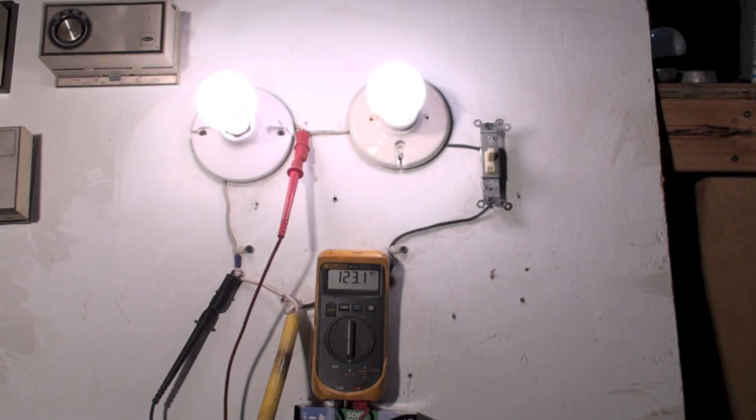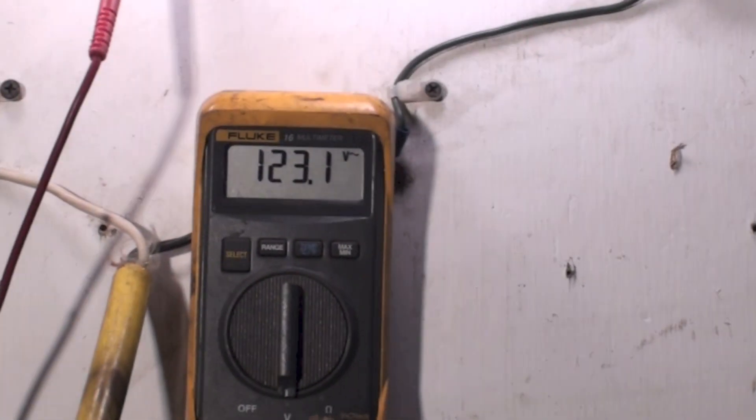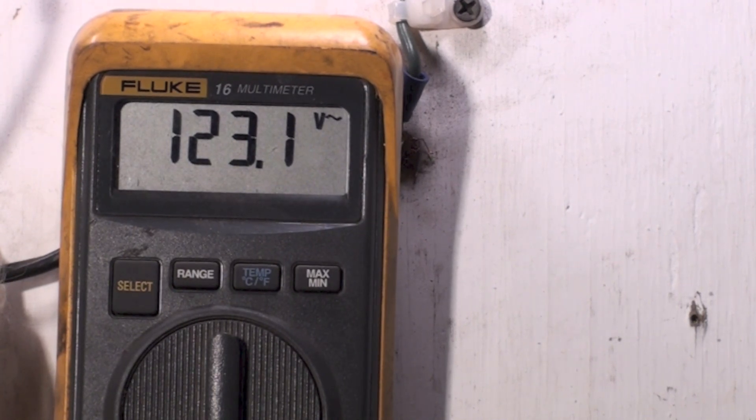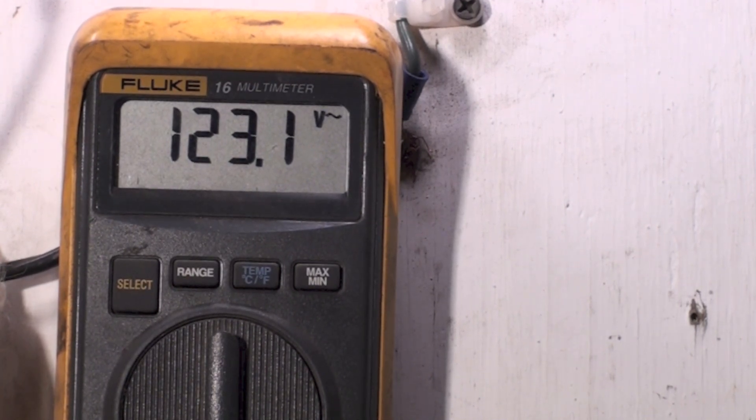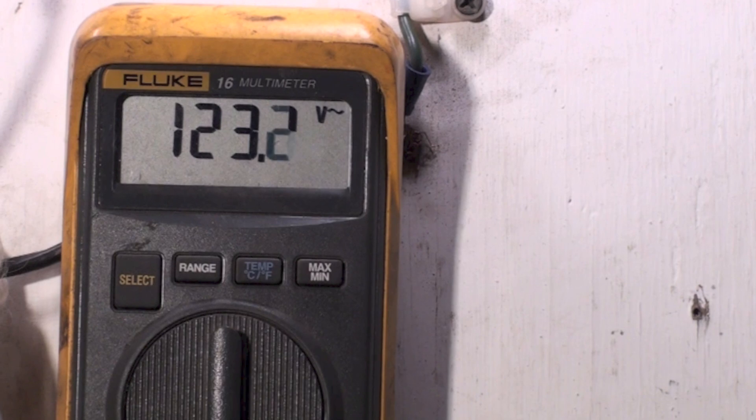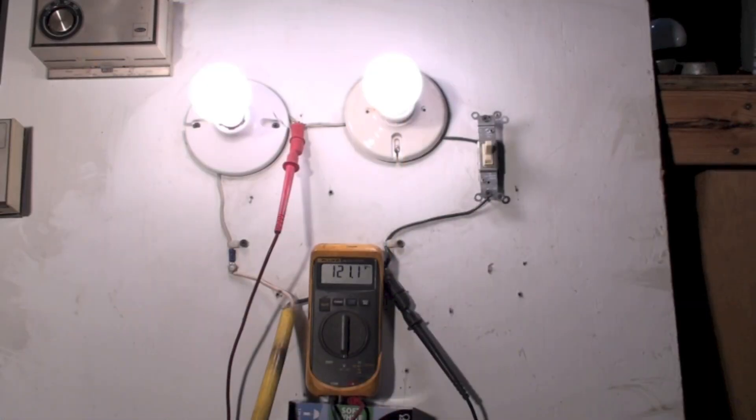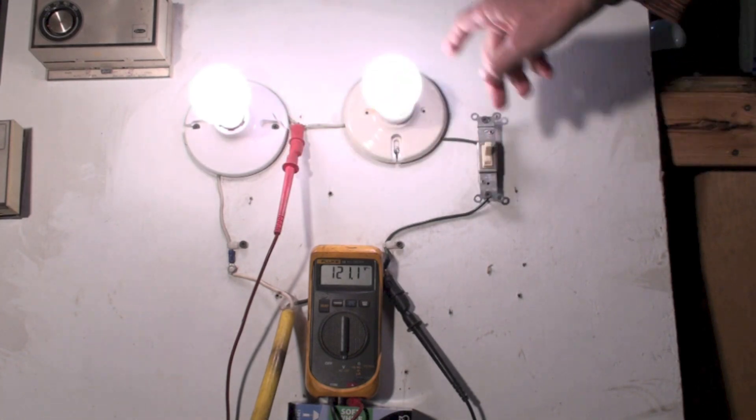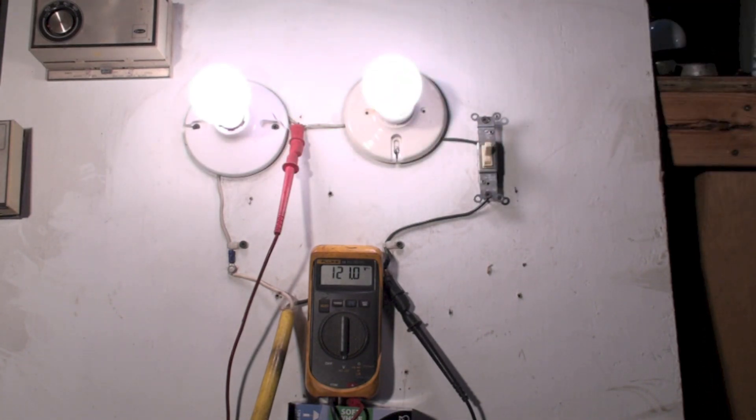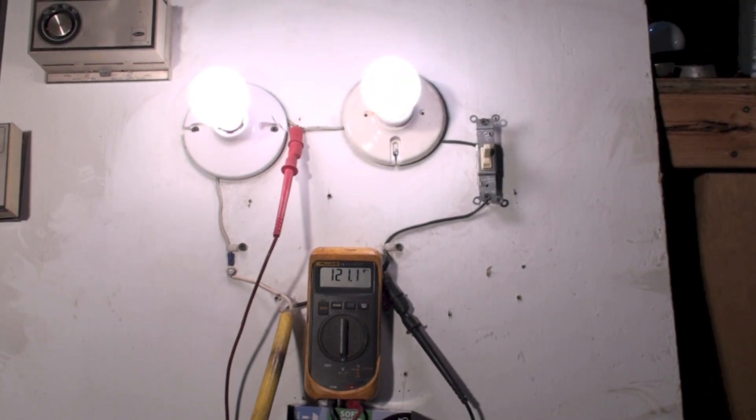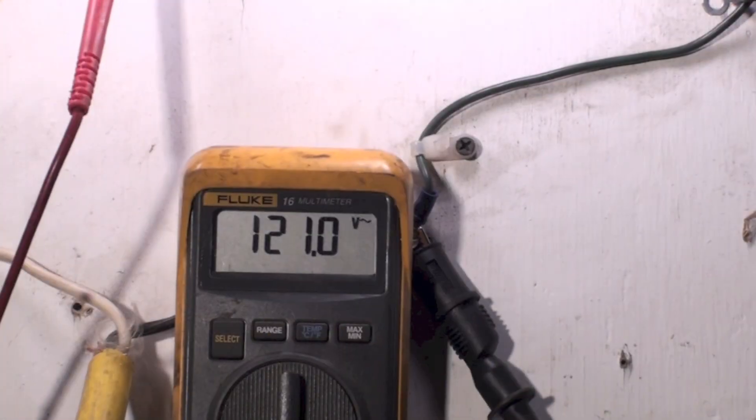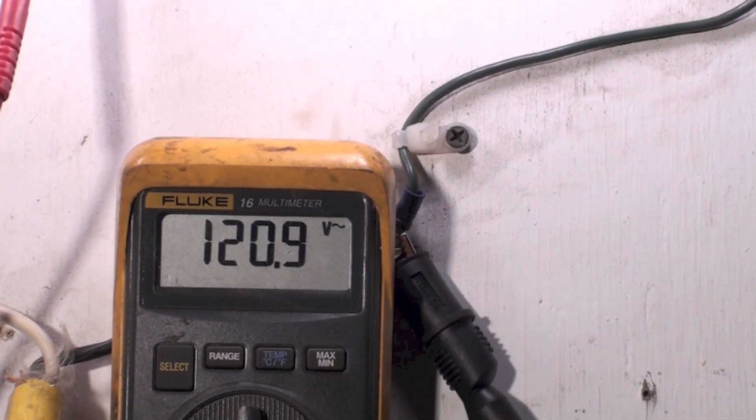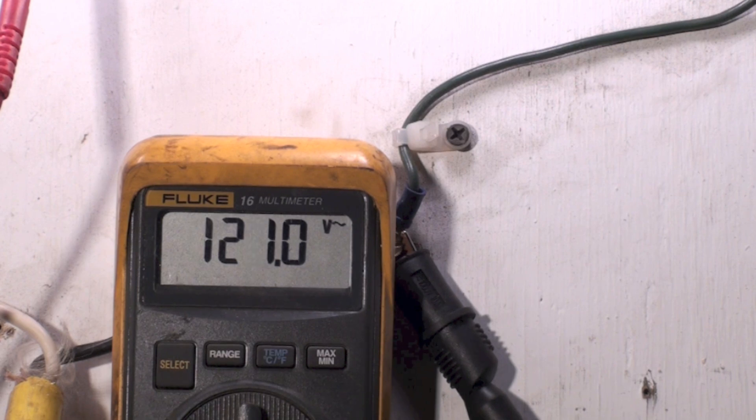You can see that voltage is 123. Let's switch it to the other light. Now if you look, I have one probe here and one probe there, so I'm testing this light. Let's see what our voltage is. It's 121, so we're a couple of volts different because no two loads are actually identical.